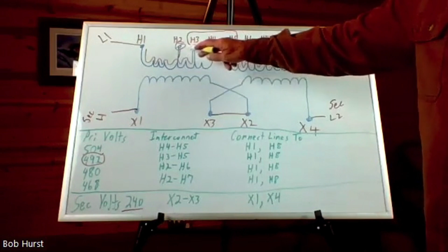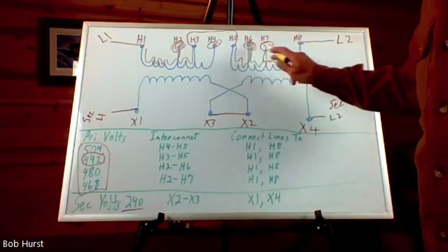So anyway, that's what we want to do. We want to connect our L1 to H1, which is going to go through here, and we find out what path based on the interconnection right here, based on our voltage, and we select this. That's our jumper, which is going to bypass however many windings we need, and the windings we don't use, we cap them off so they don't have another path to ground or another path to a circuit.